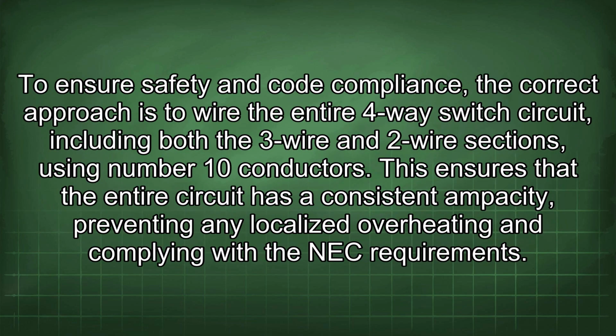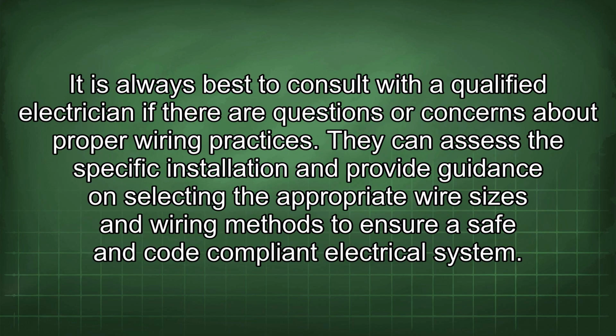To ensure safety and code compliance, the correct approach is to wire the entire four-way switch circuit, including both the 3-wire and 2-wire sections, using number 10 conductors. This ensures that the entire circuit has a consistent ampacity, preventing any localized overheating and complying with the NEC requirements. It is always best to consult with a qualified electrician if there are questions or concerns about proper wiring practices. They can assess the specific installation and provide guidance on selecting the appropriate wire sizes and wiring methods to ensure a safe and code-compliant electrical system.